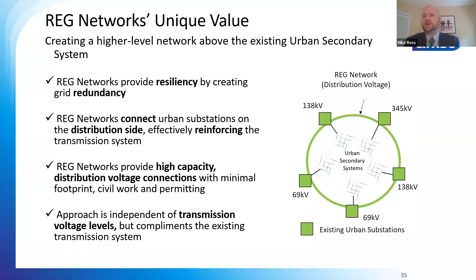Next slide, please. So specifically, the project in Chicago, the goal is to interconnect a number of substations in the downtown Chicago area to increase the reliability and resiliency of those substations. And what makes it important for the specific project is that in downtown Chicago, there are two substations that are fed radially. So they're fed from one source at 69 kV. And then a third substation that's connected by multiple sources at 138 kV. And the goal is to interconnect all three of these substations together so that if you have a problem with the transmission to any one substation, we can move power through the superconductor cables and keep the lights on during those events. And that in turn increases the overall reliability of the network.